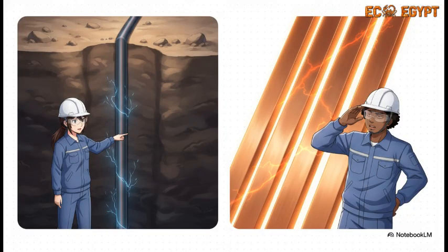As you might guess, the cables you need for medium voltage versus low voltage are vastly different beasts. MV cables are totally optimized for extreme voltage over long distances. In standard designs, we're usually talking about 3-core, 120 square millimeter aluminum XLPE cables. And for safety, these are buried a full meter deep in clean sand trenches.